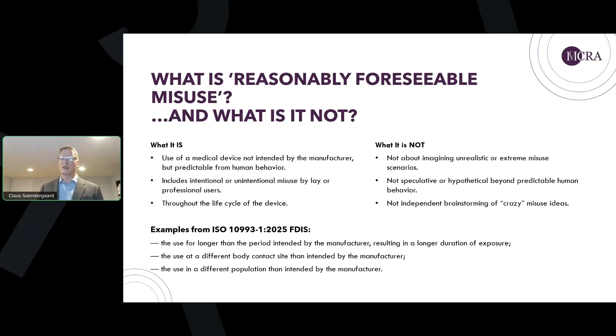So outside of the scope of what this might mean, it's also equally important to remember that, as I said earlier, it's not about biocom specialists or regulators sitting independently and coming up with these misuse scenarios. Really, the reasonable foreseeable misuse concept is something that should be baked into both your initial design phase and the life cycle of the device, as we previously talked about. So it's more of a team effort and a part of your overall risk management process, and not an event that happens out of context.